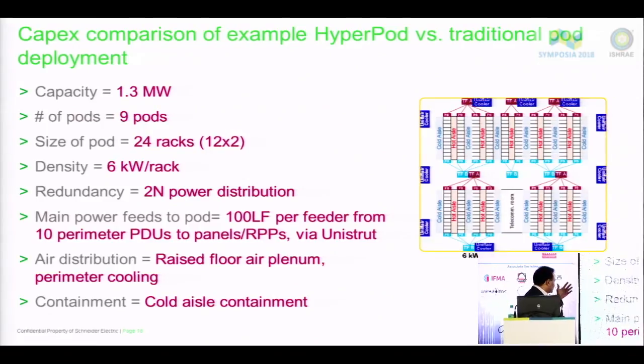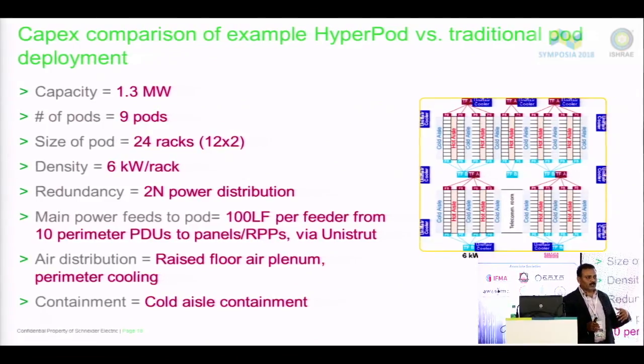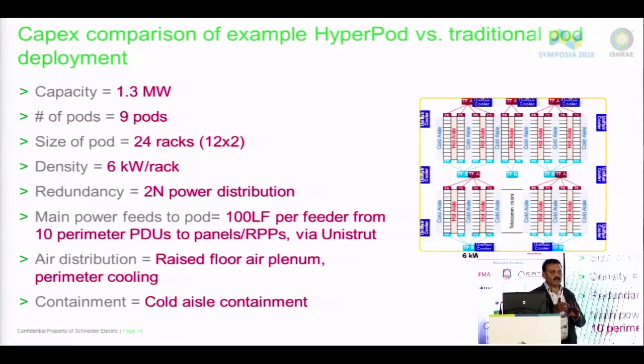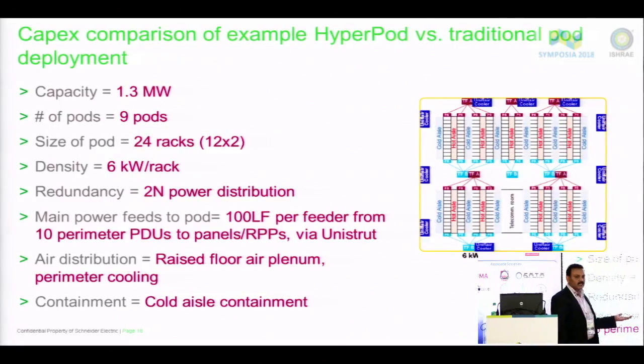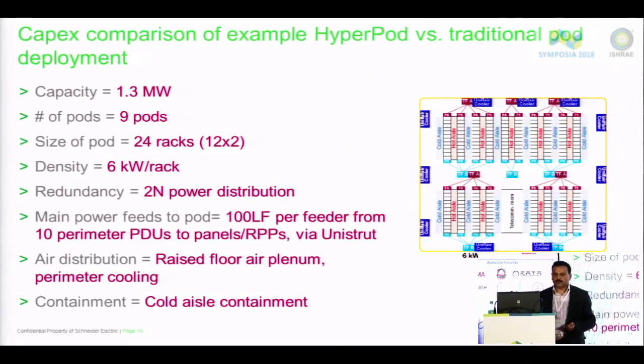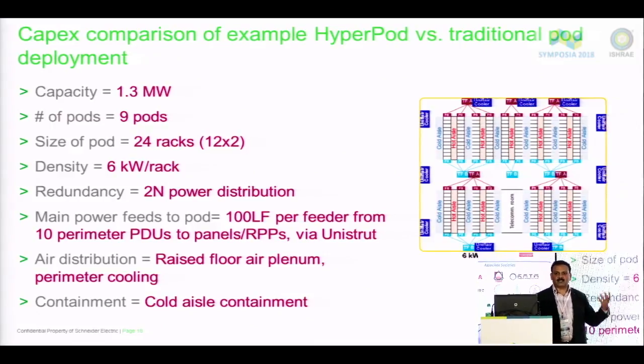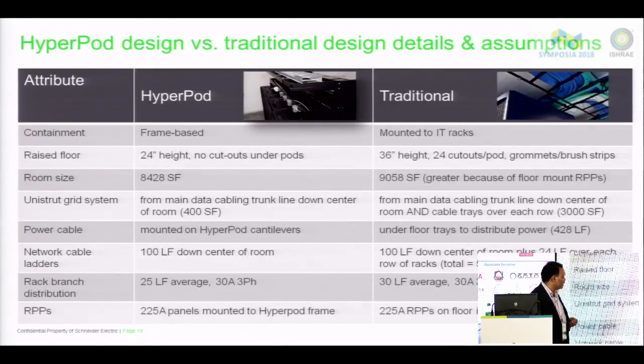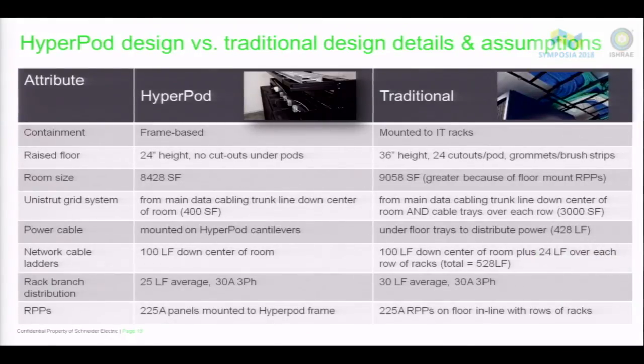But these are the configurations which were looked into, right from data cabling, power cabling, and distribution paths. Air distribution was through a raised floor air plenum, and containment was cold aisle containment. That is very typical of a co-location data center. Some of the other things taken into consideration were HyperPod being frame-based as well as conventional containment mounted on the IT racks.